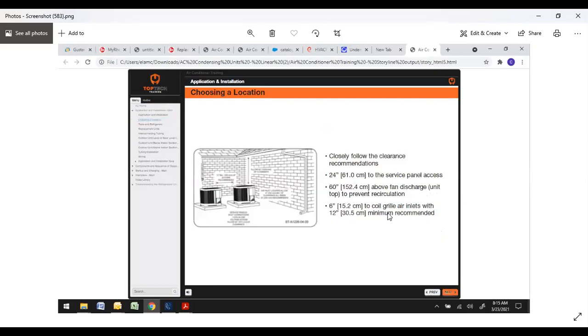Also, when choosing a location, closely follow the clearance recommendations. You do want 24 inches to access the unit, to service it, and at this point while you're installing it. They do recommend 60 inches above for proper discharge, and then also 6 inches from coil grill inlets, but they really recommend 12 inches minimum. So it is important. The 60 inches discharge on top is real important. So you don't want to put it under decks with a very short clearance. You will end up with some higher than normal discharge pressures, and that will affect operation and operating costs.